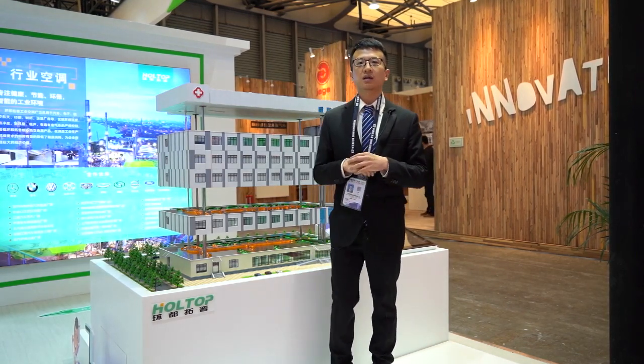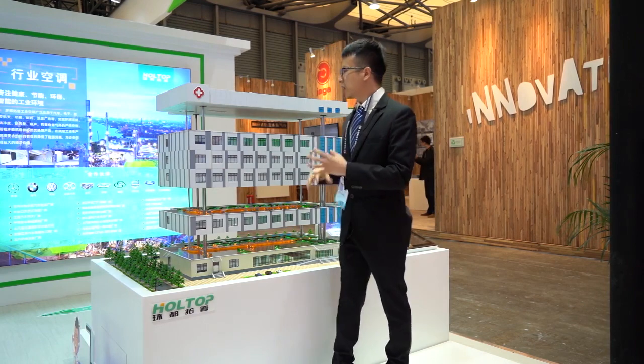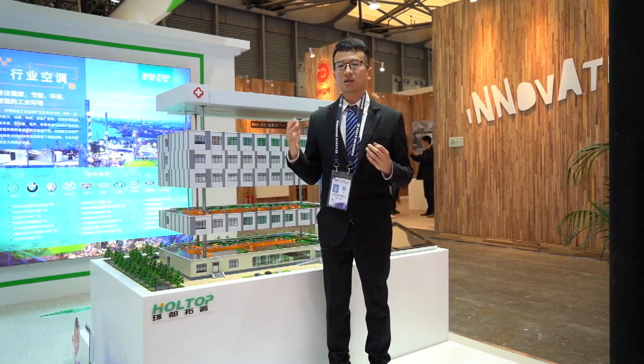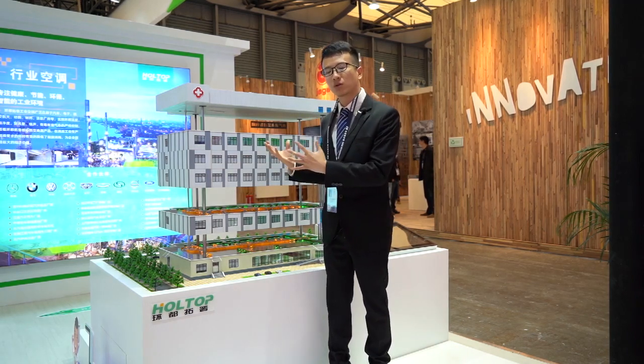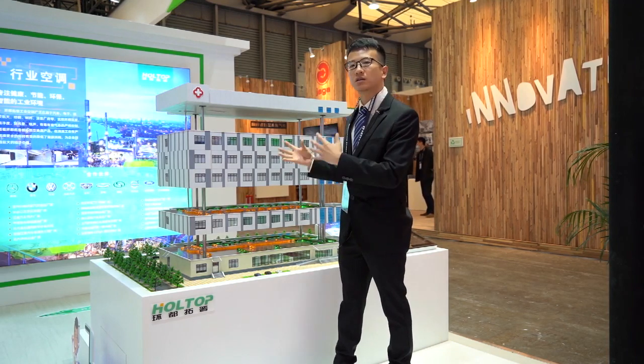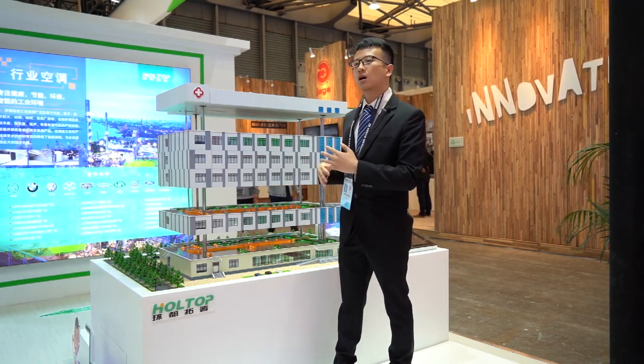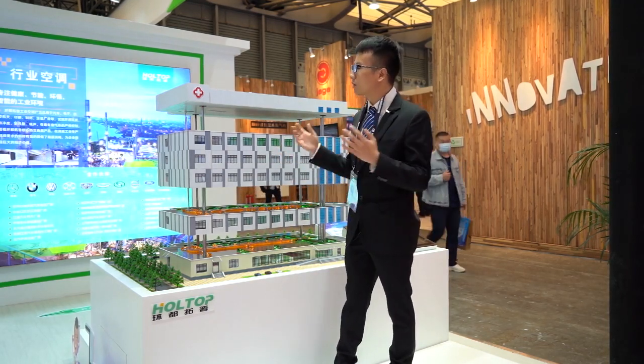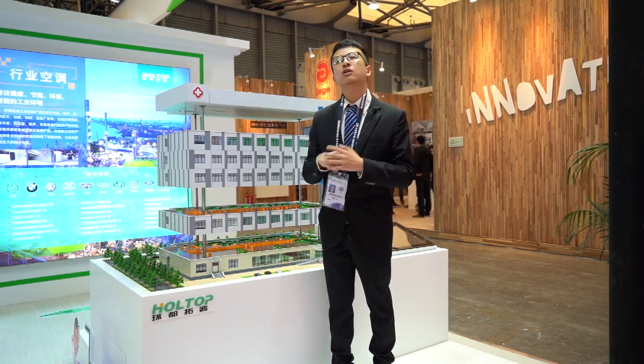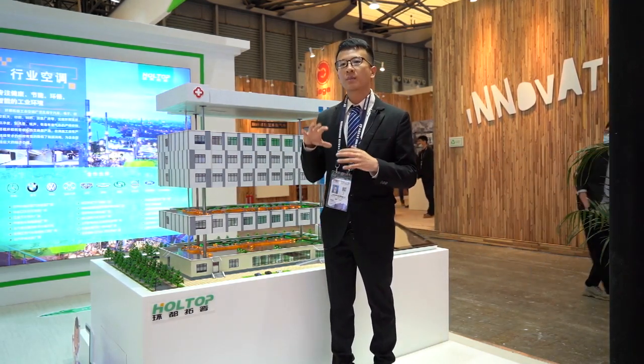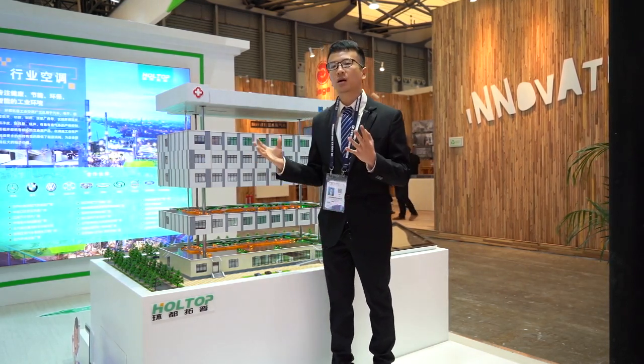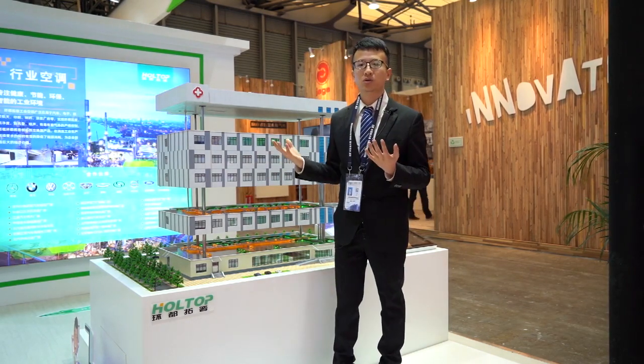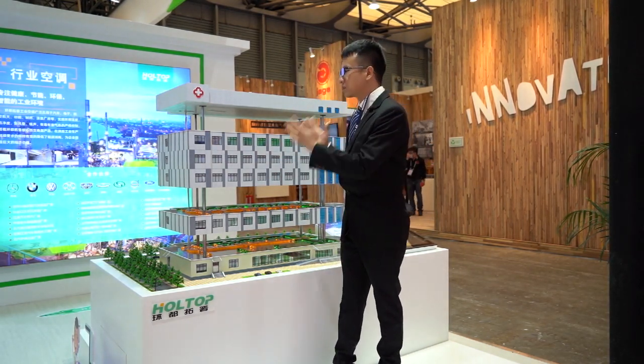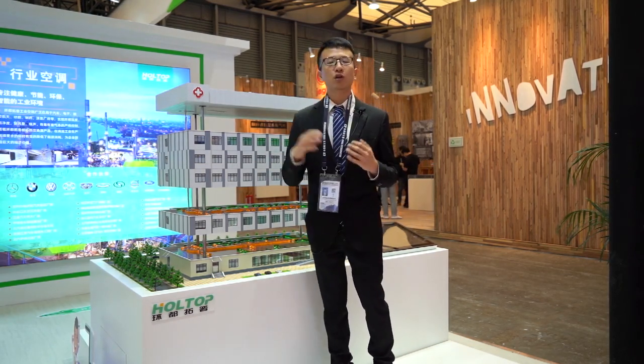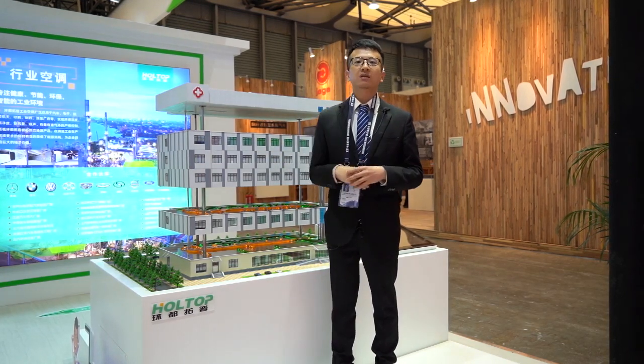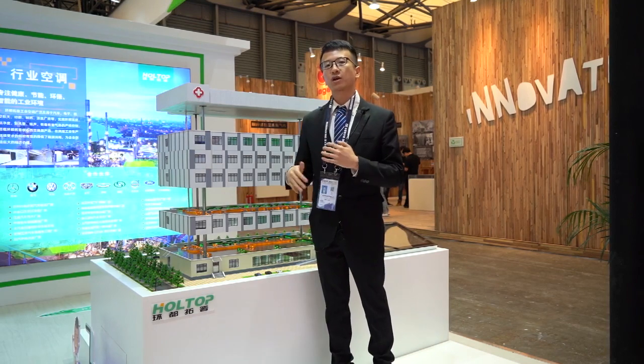The third one is the ventilation operation time. As we know, in hospitals in China, the standard is 6 air changes per hour, which means the smart fresh air system should be operating 24 hours a day. But as we said before, when the smart sensor detects no one in the room, the fresh air can operate at a minimum level, and you can use the other fresh air for other rooms where there are more people. In this way, we can supply enough fresh air to each room, but with very low energy consumption.